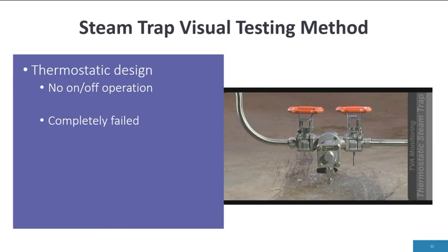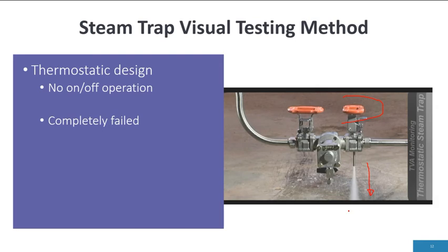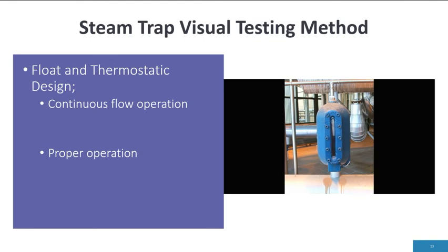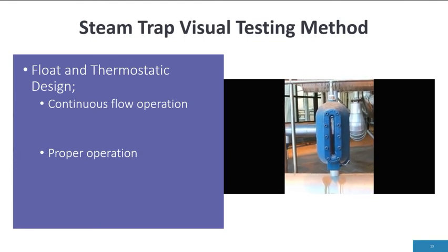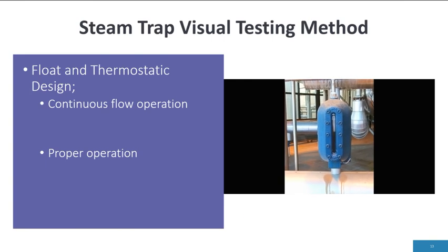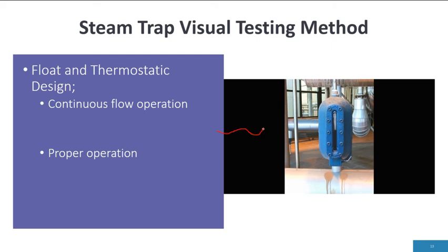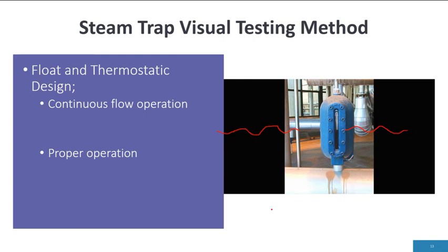A thermostatic design steam trap should show no on-off operation, or if completely failed, it will stay open. As the handle is activated, you'll see the discharge — it never shuts off, completely failed, blowing through. This type of steam trap does not have a distinct on-off operation in all cases, so continuous flow can also represent proper operation. This happens to be another type of visual indication, which is a sight glass inside the steam trap body.